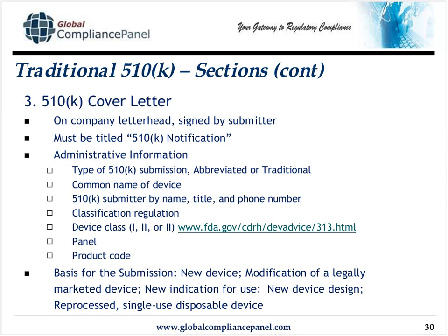The administrative section contains the type of 510K submission. Is it an abbreviated one or a traditional one? The common name of the device, the 510K submitter, who they should call or contact, not just by name, title, and phone number, but obviously email address also. What classification regulation and device classification I'm referencing that this device falls under. The classification panel and the product code as well.